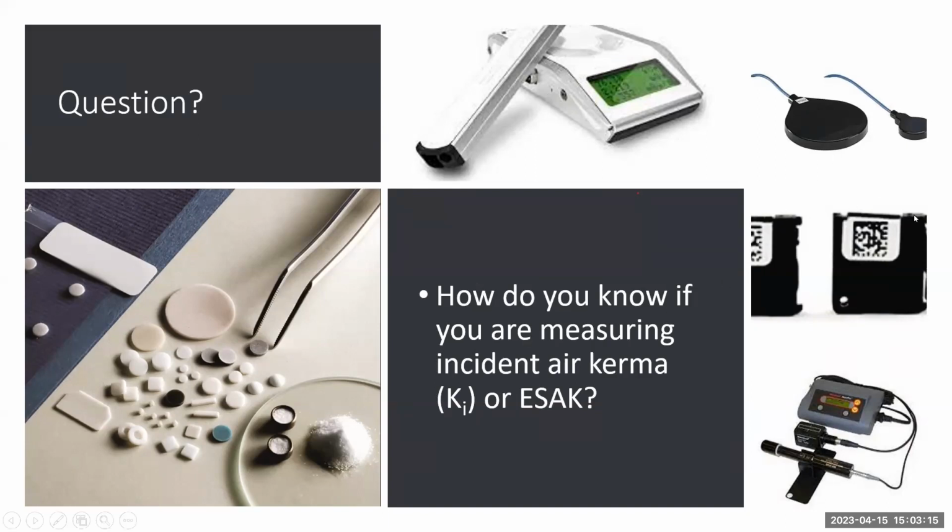But if you have other things like ion chambers that don't have this lead back, or OSLDs or TLDs, putting them on the patient, then these detectors will likely capture the backscattered radiation, and therefore what you're measuring at that point is entrance surface air kerma.